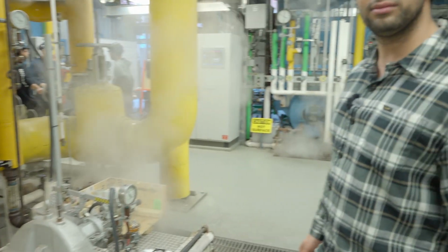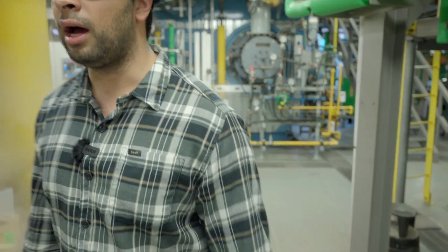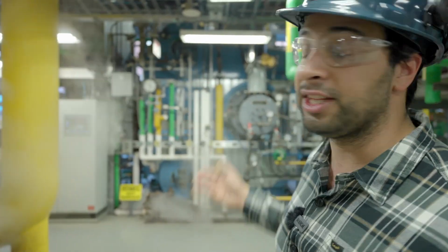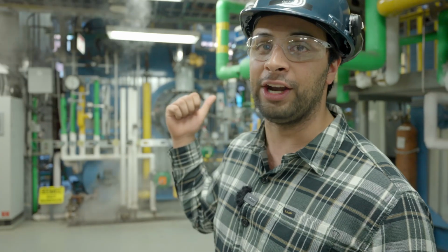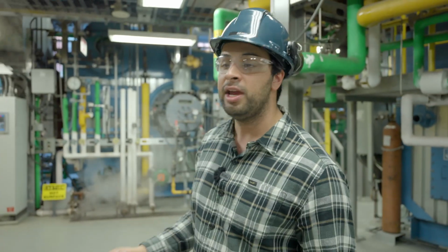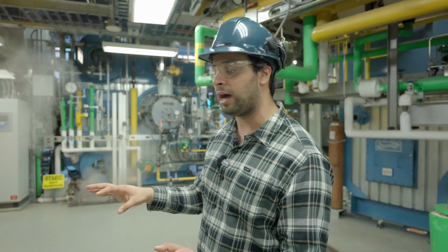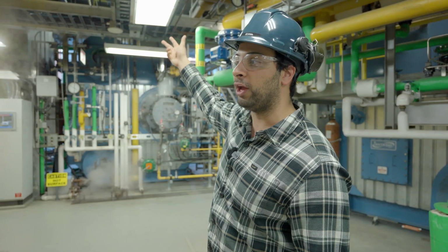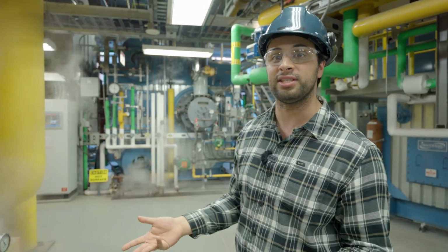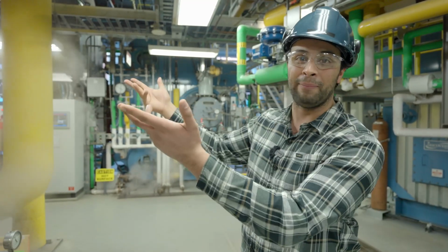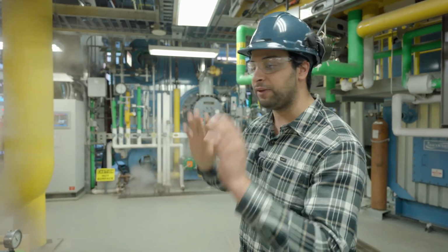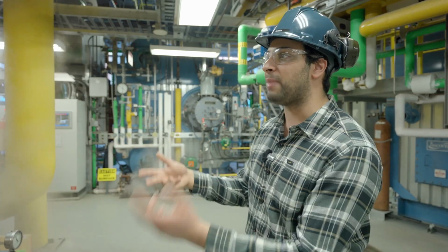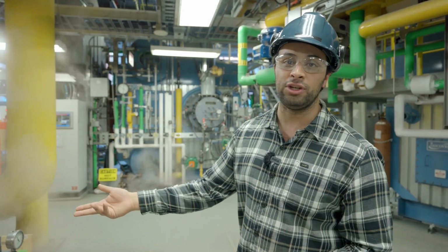Well, how do you manage the condensate? One of the ways we do it is right from the beginning. Once we get the boiler up and running, like this morning, we were stone cold. There was no pressure in the header, no pressure in the boiler. So what we do is we open up all of the bypass valves for the steam traps. We open our non-return valve on the boiler, and we just let steam start to flow through all the systems. And what that does is it warms up all the pipes, warms up all the components. Once we've got steam coming out of there so that cold air isn't causing it to condense, we close those back up. And then we can just let the steam traps do their job from there.